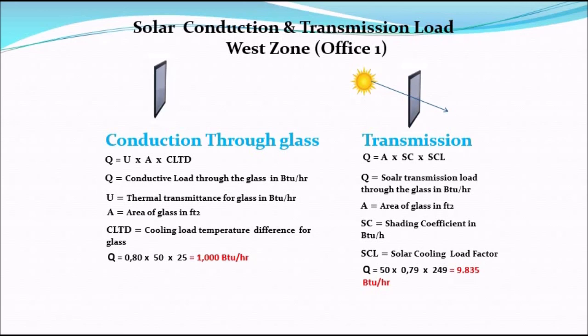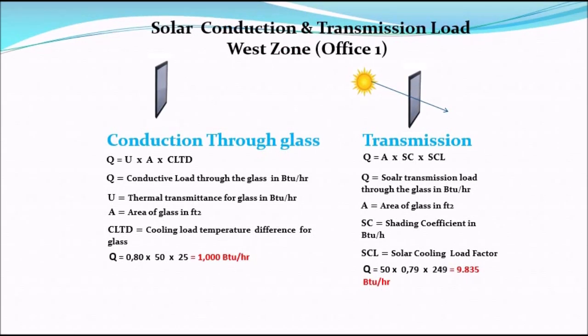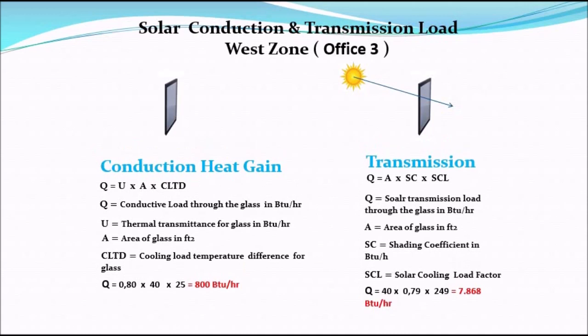The next thing to calculate is the transmission load through the glass. To determine the transmission load, we use the formula Q = A × SC × SCL, where Q is the transmission load through the glass, A is the area of glass in square feet, SC is the shading coefficient, and SCL is the solar cooling load factor. Plugging in the numbers gives a total transmission load of 9835 BTU/hr through our glass.